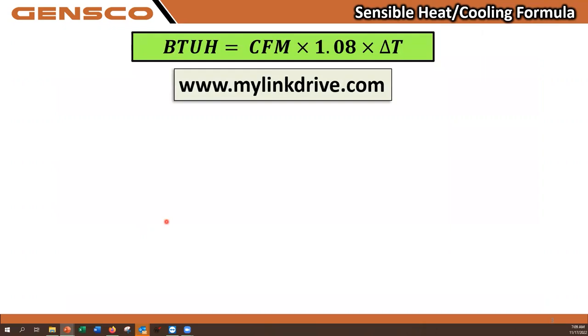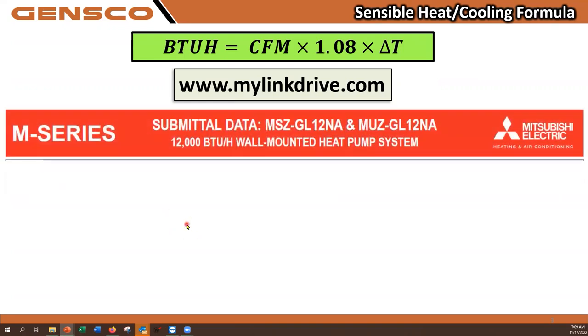The first place to go, and our example this morning is going to be using an MUZ MSZ GL wall-mounted unit because it is pretty simple, is mylinkdrive.com. Unless you already know this number, you need to find out what the CFM rating is of this unit. I'm using a ductless unit. Because there's no ductwork, you don't have to worry about measuring the air. You can go to the submittal, and if that unit is clean, filter's clean, coil's clean, blower's clean, then the rated airflow when we choose high-speed fan should be pretty close to what it actually is doing.